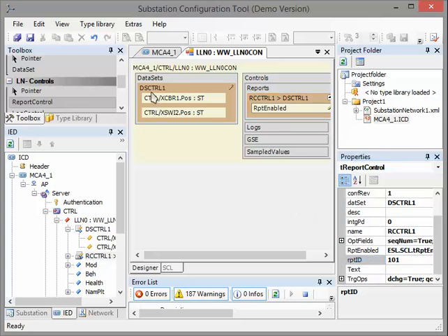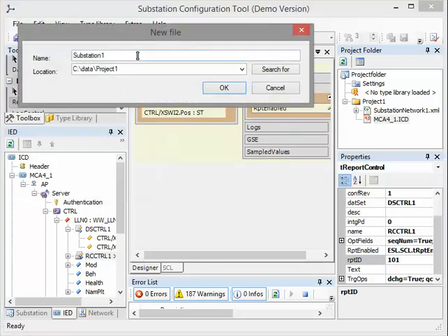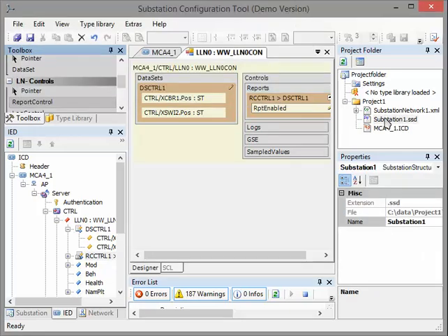So that's all. We have created our dataset and our report control block. Now we are ready to create our substation configuration file. For this, we have to add new substation information. We say File, Add, New Substation — for example, we set the name 'substation1'. This file contains information about the substation such as how many bays, what the voltage level is, and so on. This tool will only create the substation configuration file if we have added the substation file. Now we can say Save Project Folder.